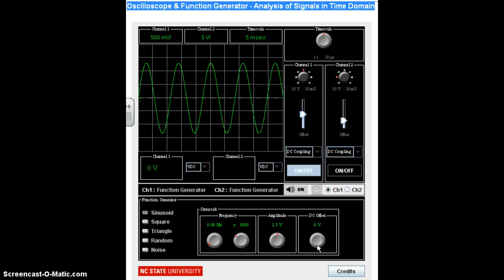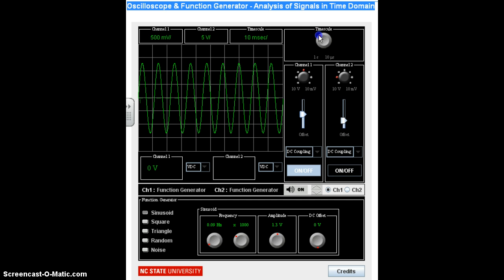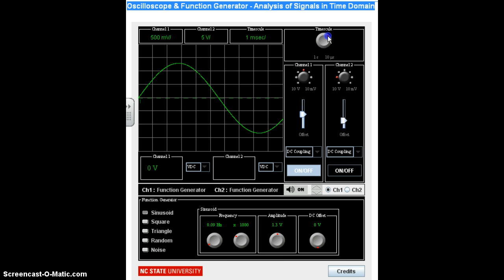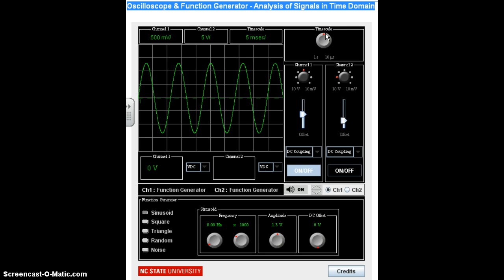Now let's look at the oscilloscope. The oscilloscope has a bunch of different knobs. The first one is the timescale knob. Since the oscilloscope can only view signals, adjusting the timescale just zooms in and out. Turning the knob to the left zooms out, and turning it to the right zooms in. This changes what's called the time per division — for example, 5 milliseconds means the space between two vertical lines is 5 milliseconds.